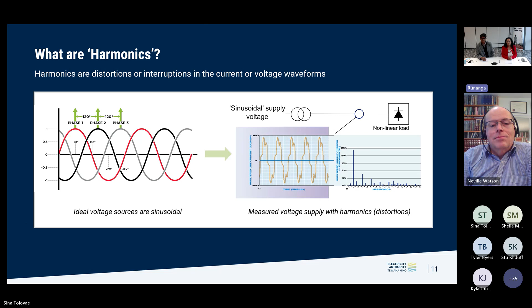Some of the common sources of existing harmonics are transformers, which happens during energization. We have industrial loads like arc welders, furnaces, ballasts, and rectifiers, and at residential levels, we have computers, switching devices, and drives. And the big ones on the network side are the capacitor banks. So these have been the common sources of harmonics, but things are changing fast in the coming years.